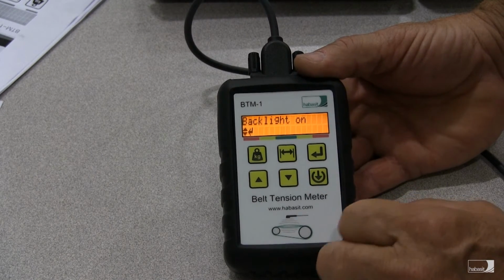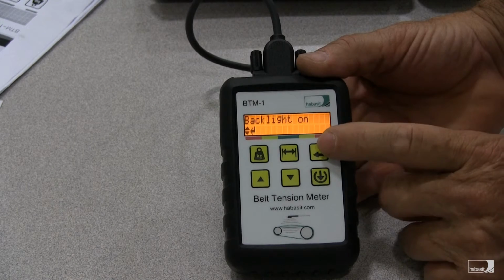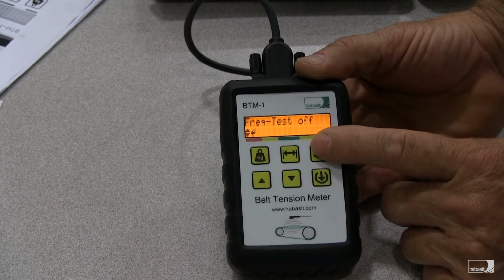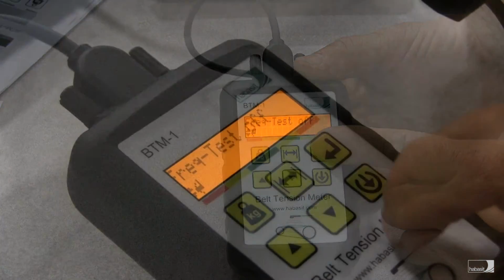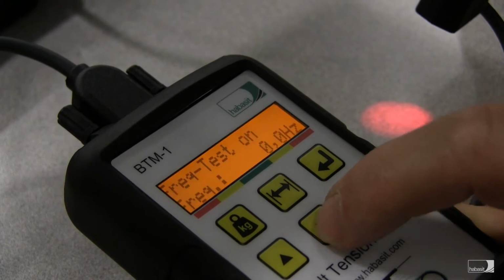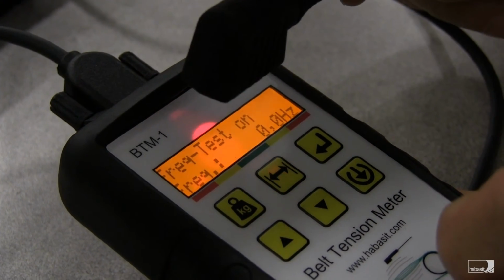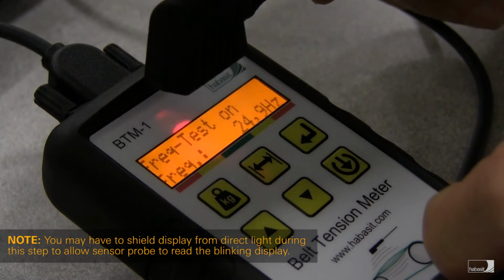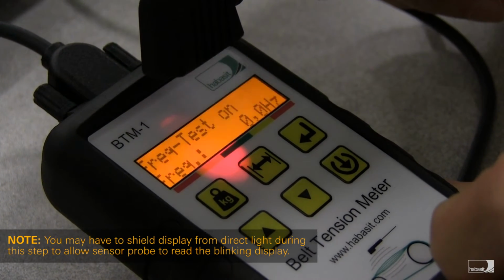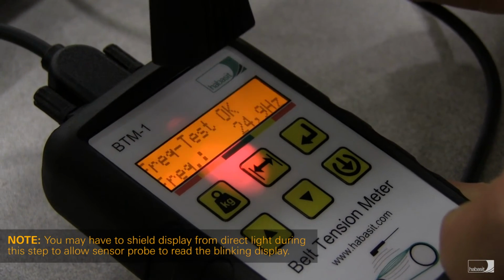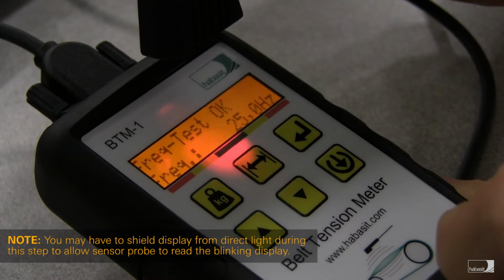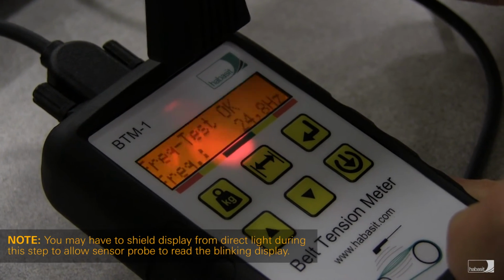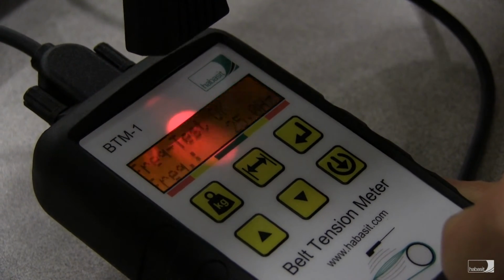And then finally, the last step in this menu is a calibration test, a frequency test. To begin the frequency test, touch the up or down arrow, hold the probe over the display until you hear an audible beep. When you hear the beep, you saw the display there was 24.7 or 24.9. The display should be 25 plus or minus 1 hertz, and the test is okay.